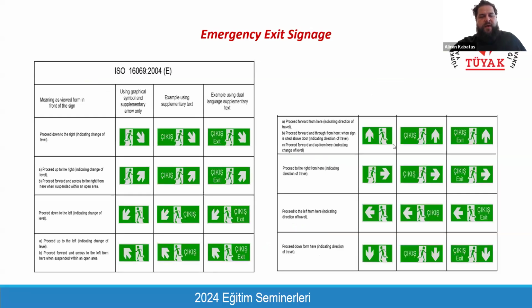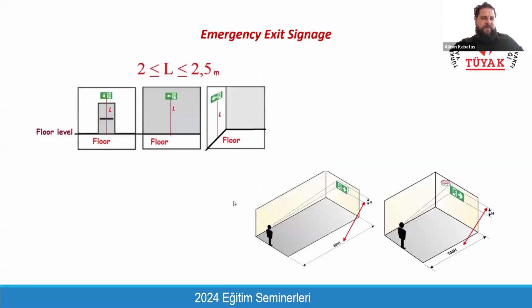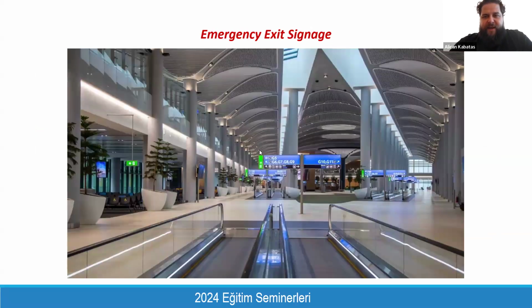These examples should be used, and we prefer to use without letters only this arrow and running man and door, because if you have a çıkış right on your plate, you need to provide the English translation as well for your international occupants. And the locations should be like that, so that the occupants can understand the exact location of the exit access door. This is an example from Istanbul Airport where we were the consultant, fire and life safety consultant. As you can see, these are the wayfinding plates, and we provided this special design so that it can be understood.